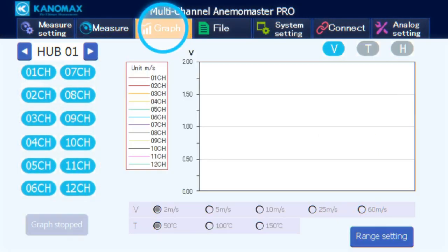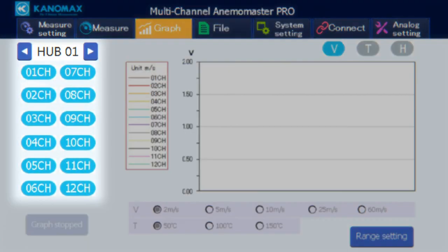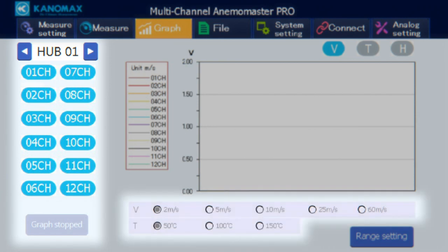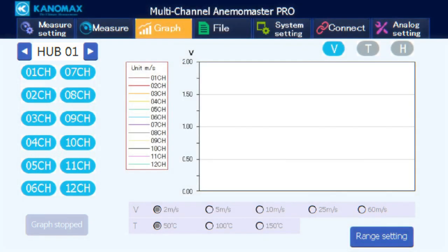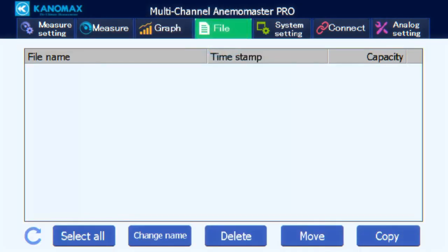Tapping the Graph tab opens the graph screen where you have similar navigation and toggle buttons as before. However, now you have a button to stop or start the graph drawing, toggles for which measured item you'd like drawn on the graph, and a range setting button that toggles the graph range between a manually set range or an automatic one. When you switch the range to manual, 2 rows become available where you can set the range for velocity and temperature. Under the File tab, you'll find a directory of all previously saved measured data.